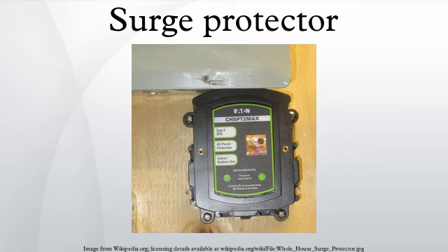Because of their good price-performance ratio, MOVs are the most common protector component in low-cost basic AC power protectors. Transient voltage suppression diode. A TVS diode is a type of Zener diode, also called an avalanche diode or silicon avalanche diode, which can limit voltage spikes. These components provide the fastest limiting action of protective components, but have a relatively low energy absorbing capability. Voltages can be clamped to less than twice the normal operation voltage.